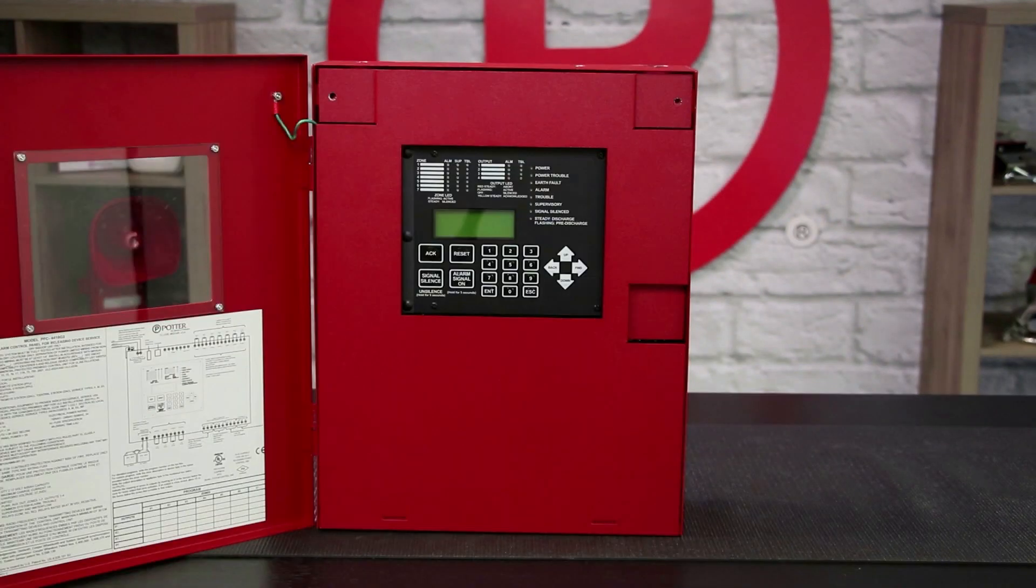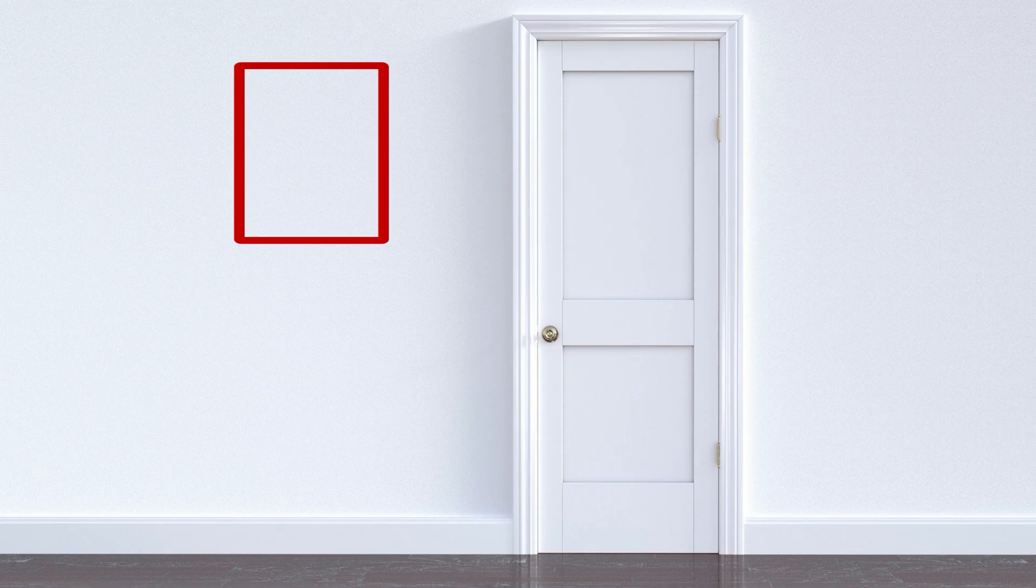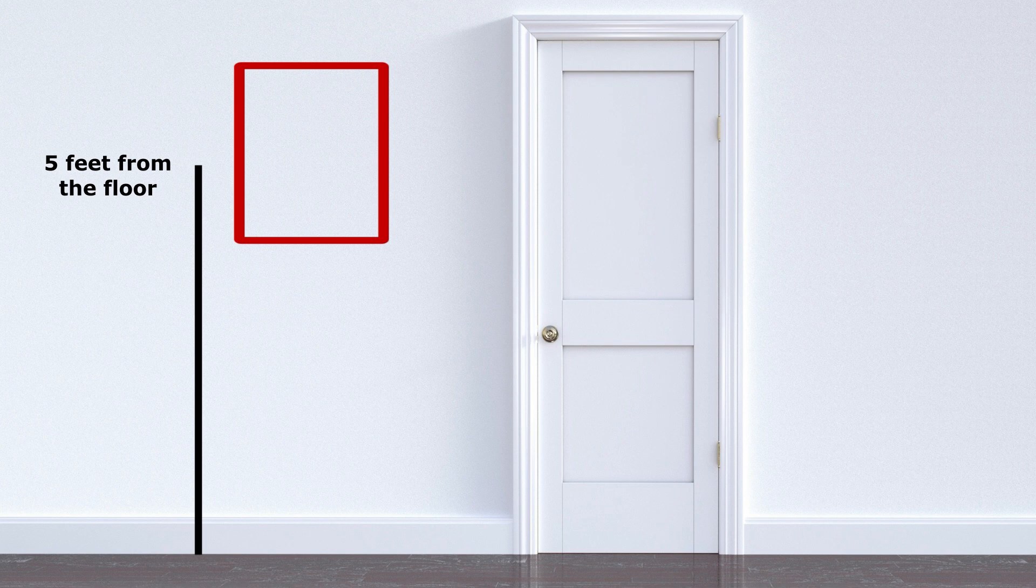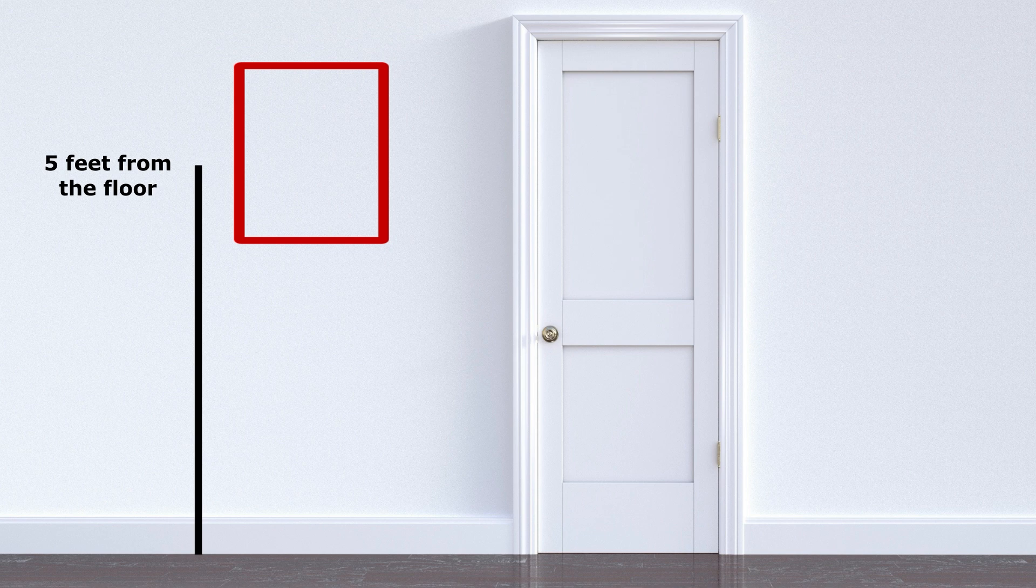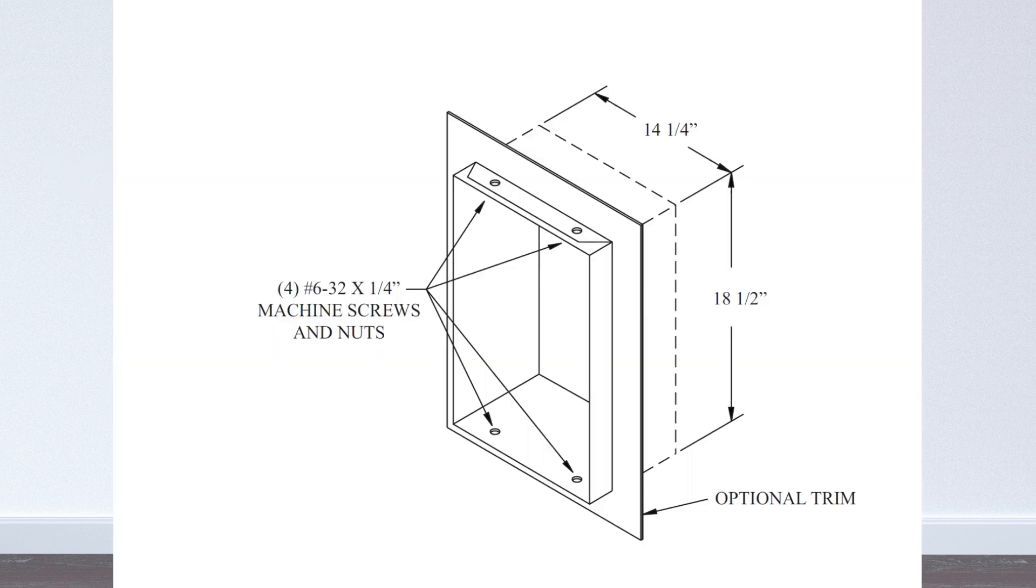If this is a new installation, remember that the enclosure should be mounted in a convenient location, approximately five feet from the floor, where it will be accessible for testing and service. The enclosure may be surface mounted or semi-flush mounted using an optional trim bezel.